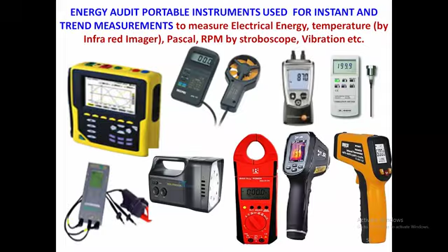A power quality analyzer, because power quality is definitely made mandatory now. Even our inverter compressor or inverter fridge is having so much harmonics, H5 and H7, especially on 3-phase systems and especially in industry. This is creating havoc now. And then instant clamp-on power meters, then the thermal imagers, then the anemometers and the static pressure Pascal meters, etc.